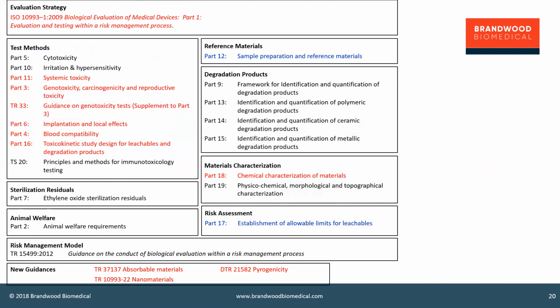Now, the good thing about the ISO 10993 biocompatibility standards is that these days there is a considerably greater emphasis on chemistry than on immediate resort to biological testing. The various animal tests and cell culture tests and so on that are done in biocompatibility testing are expensive, they're slow, and difficult to interpret at times. But if you can do good chemistry, if you can characterize the device by doing a chemical characterization, you may be able to show that you've got nothing to worry about. And particularly if you're able to show that your 3D printed metal device, for example, actually is chemically and physically equivalent to a mass-produced surgical alloy device.